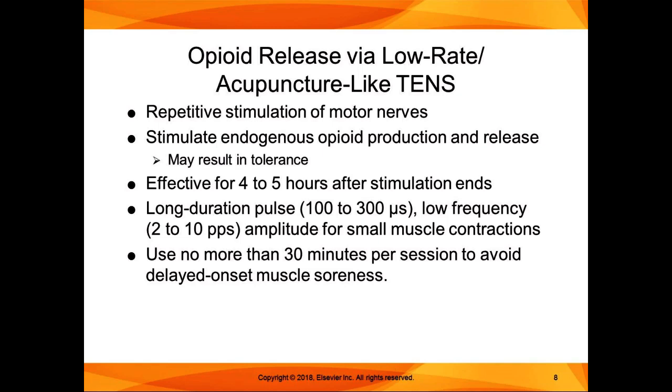So basically, we had a short duration pulse because we're going for sensory stimulation with the conventional TENS. With the low rate TENS, we have a longer duration pulse because we're going for motor stimulation. So 100 to 300 microseconds, and low frequency, 2 to 10 pulses per second.